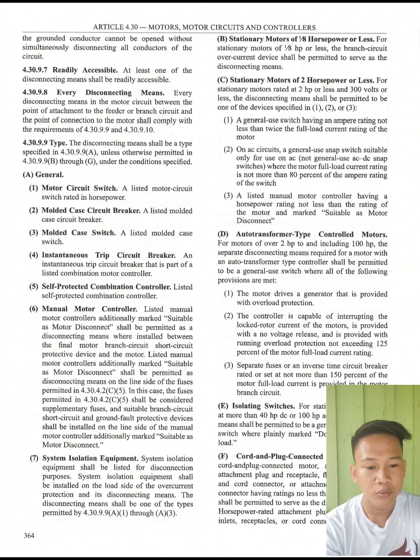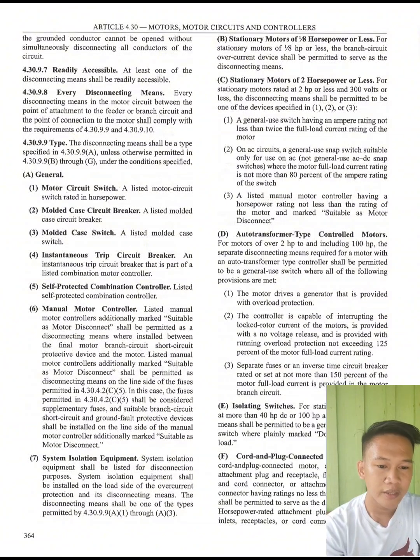C. Stationary motors of 2 horsepower or less. For stationary motors rated at 2 horsepower or less and 300 volts or less, the disconnecting means shall be permitted to be one of the devices specified in 1, 2, or 3. So, first, 1. A general-use switch having an ampere rating not less than twice the full-load current rating of the motor. 2. On AC circuits, a general-use snap switch suitable only for use on AC, so not general-use AC/DC snap switches, where the motor full-load current rating is not more than 80 percent of the ampere rating of the switch. 3. A listed manual motor controller having a horsepower rating not less than the rating of the motor and marked suitable as motor disconnect.